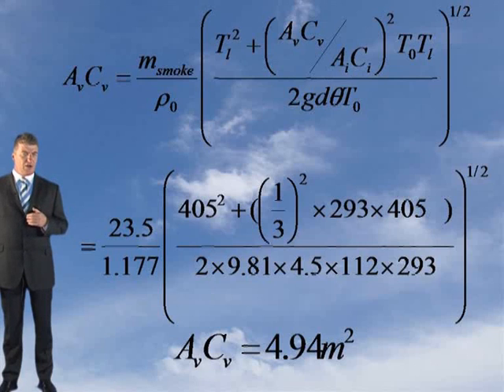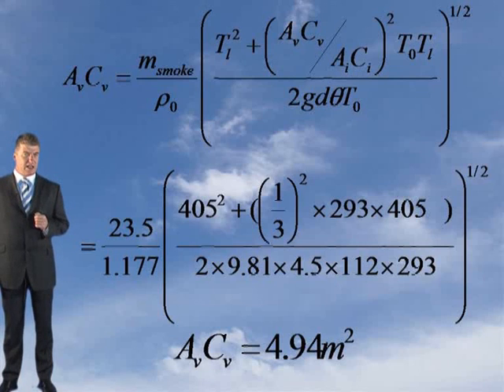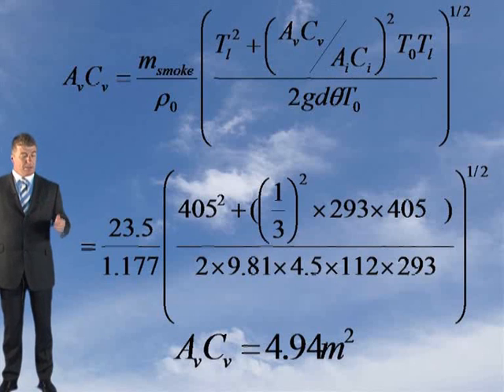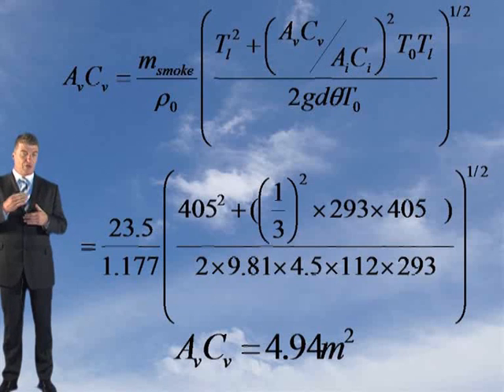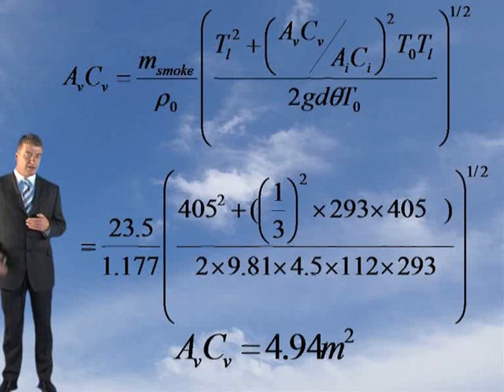The key thing to remember here is, if you look at your AVCV AICI, it's 1 divided by 3. Because there are four reservoirs, wherever the fire is, that's the reservoir where the smoke is going out. If all three remaining reservoirs are available, you've got three for the inlet. So remember that when you're doing this calculation.